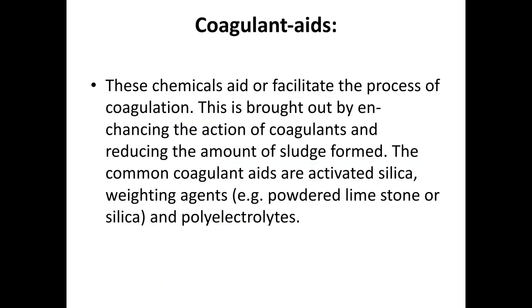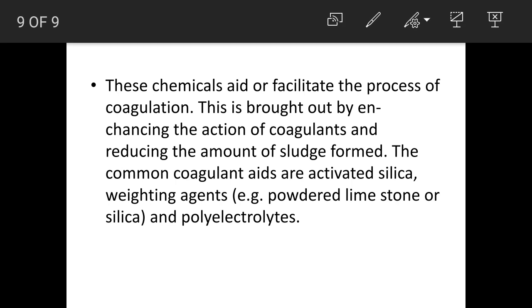The second type is coagulant aids. These are chemicals that aid or facilitate the process of coagulation. Coagulant aids can enhance the action of coagulants and reduce sludge formation. The coagulant aids used are activated silica, weighting agents such as powdered limestone, silica, and polyelectrolytes.